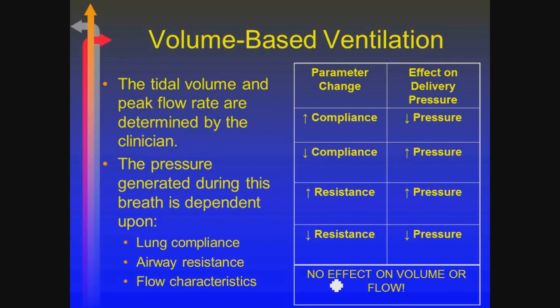Those two parameters are dictated by us. The pressure generated during the breath is dependent upon the lung compliance, the airway resistance, and to some extent, the shape of the flow pattern, which I'll just say that and we'll talk about it later. So I'm throwing a lot at you today.